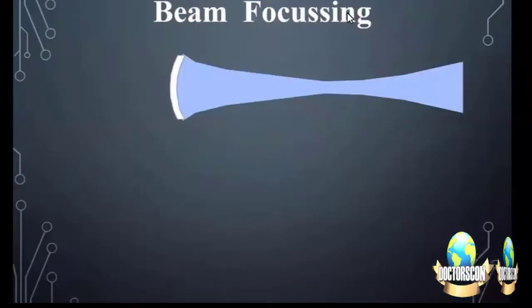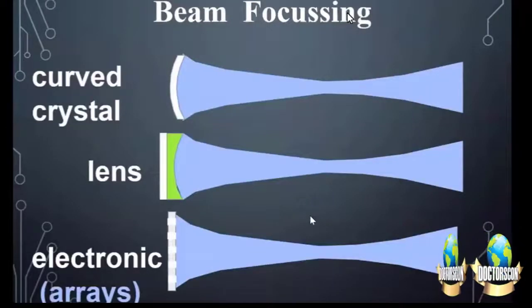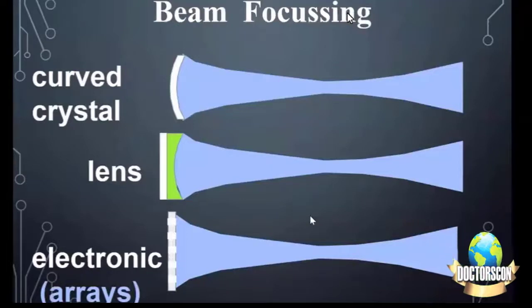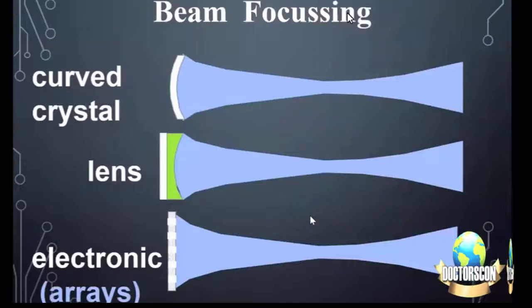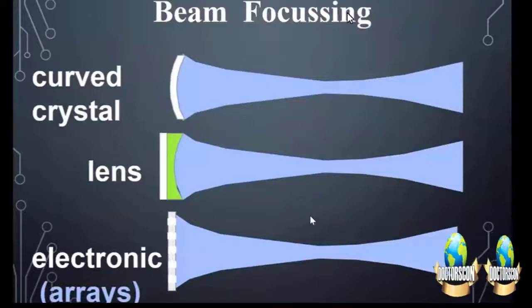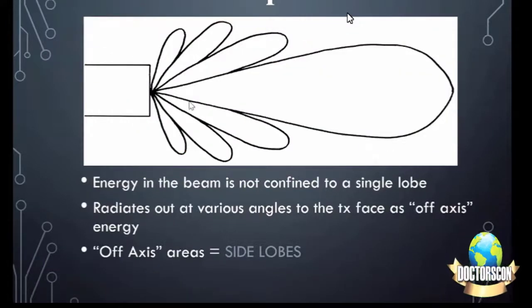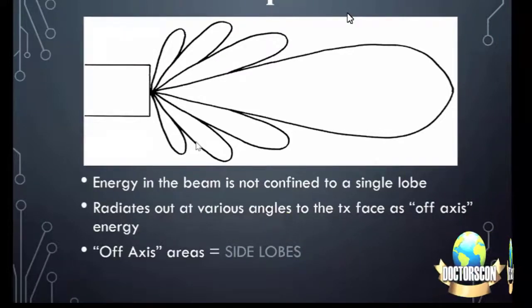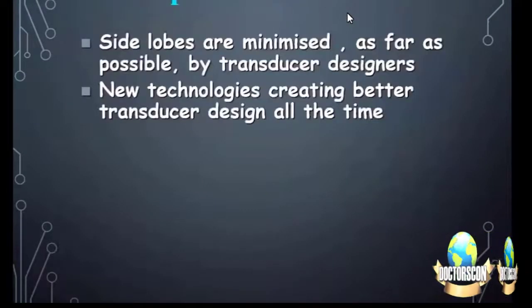This is curved crystal, the lens, and electronic array. This is how the beams are produced. Keep in mind the beams are three-dimensional. So an image requires a very narrow beam, and focusing allows improvement. There are side beams, and focusing allows us to concentrate on the center beam. This is our focus. In addition to it, there are multiple side beams which are produced. Here you can see, which can create some artifacts.